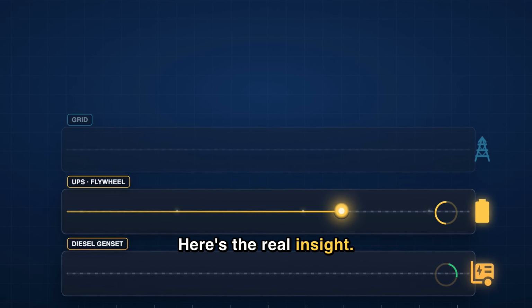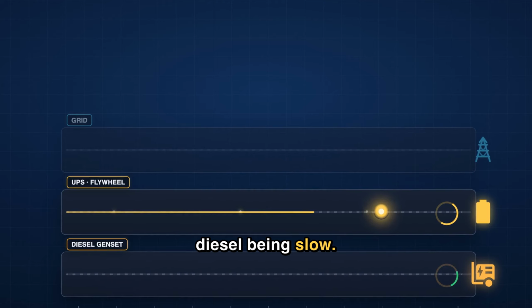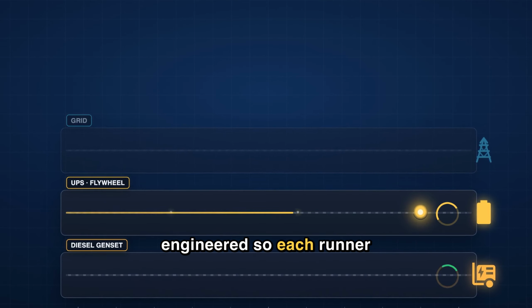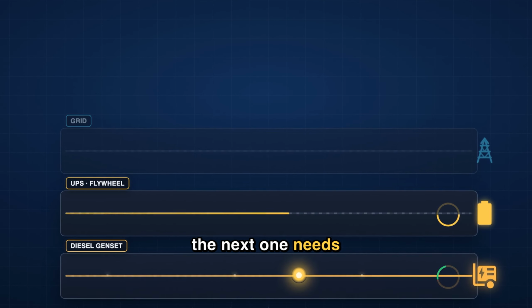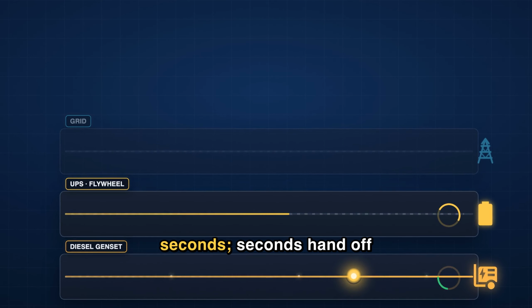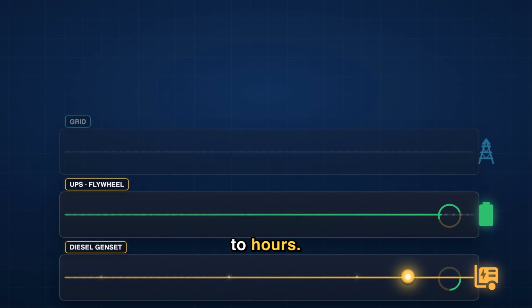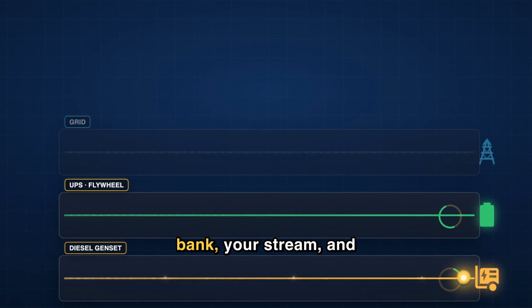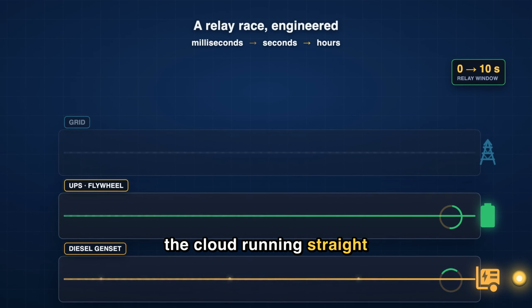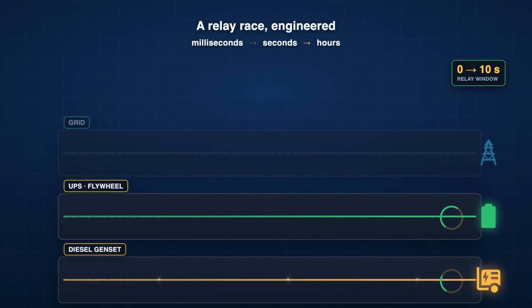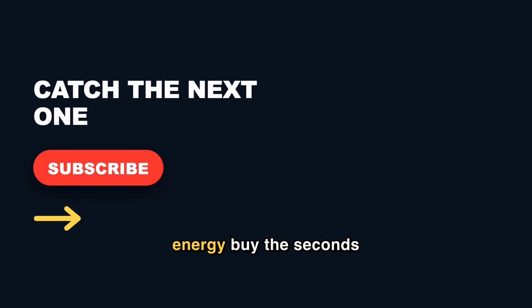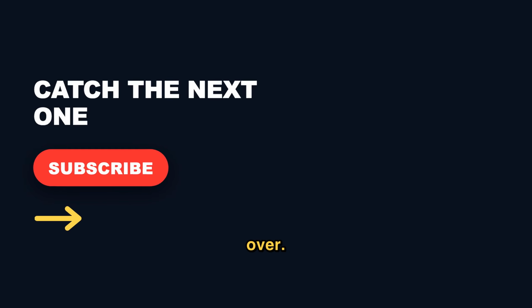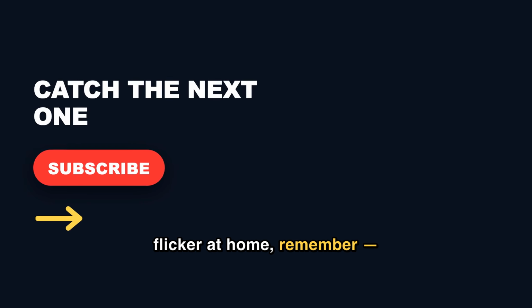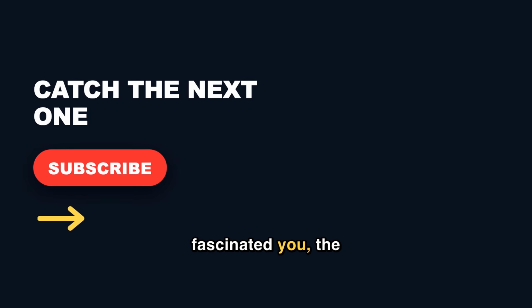Here's the real insight. Those 10 seconds aren't diesel being slow. They're a relay race, engineered so each runner covers exactly the stretch the next one needs to arrive. Milliseconds hand off to seconds. Seconds hand off to hours. That invisible choreography is what keeps your bank, your stream, and the cloud running straight through outages you never even notice. So that's the trick. Milliseconds of stored energy buy the seconds diesel needs to take over. Next time the lights flicker at home, remember, somewhere a data center just didn't. If the handoff itself fascinated you, the switching hardware that makes it seamless is a whole story of its own.